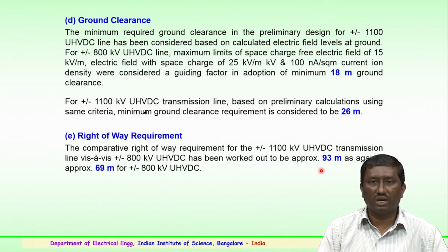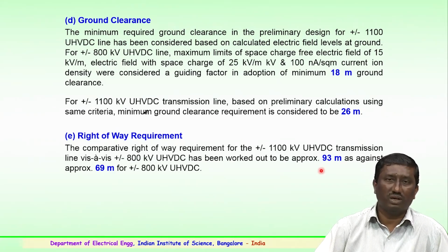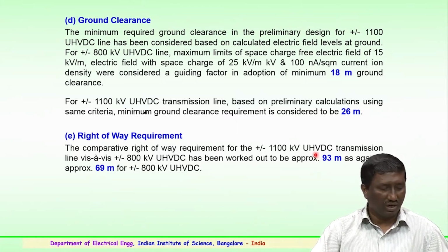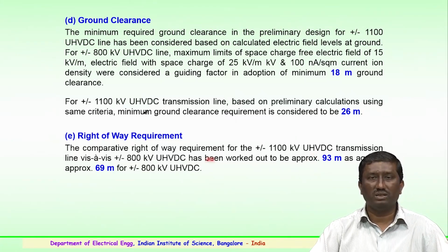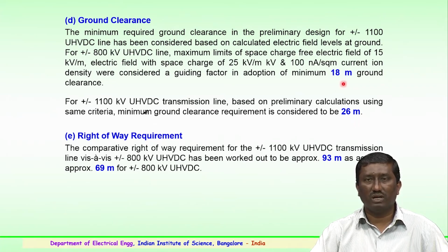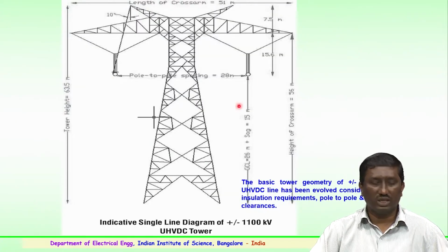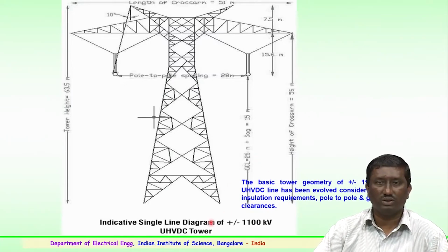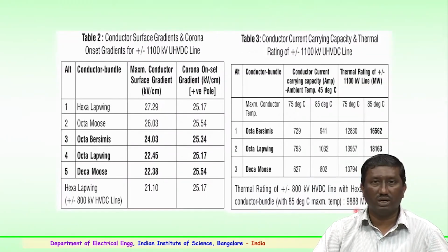So, several towers are likely to come, on long distance lines of thousands of kilometers, and several aspects have to be considered before the final designs are cleared. So, the right of way requirement will be 93 meters in lieu of 69 for 800 kV. The ground clearance will go up to 26 meters, whereas for 800 kV it is 18 meters. So, this is again a typical similar tower with the same clearances, as I have indicated.